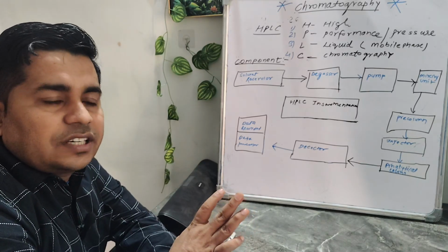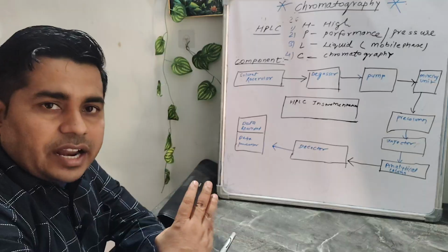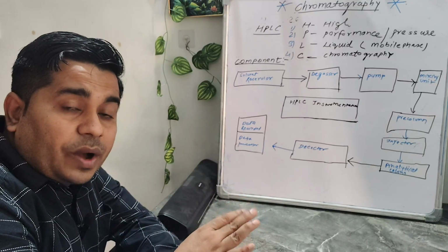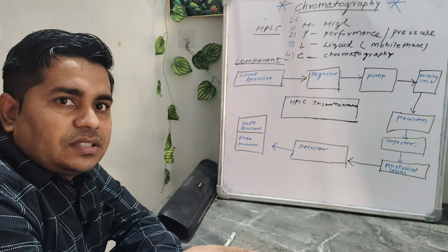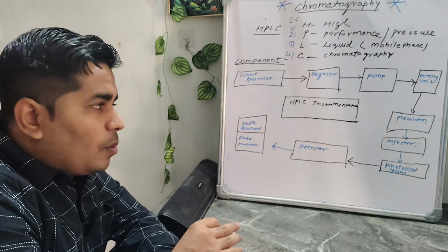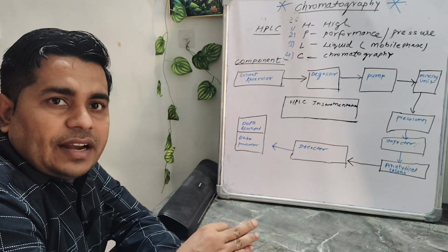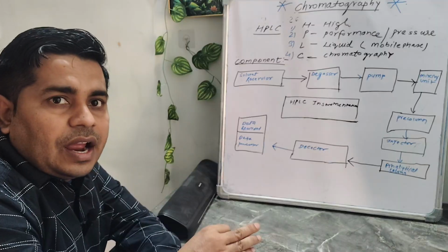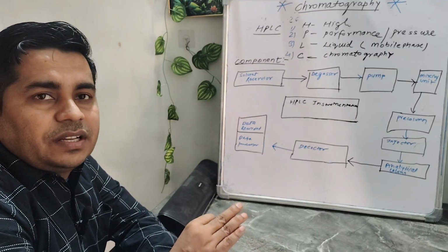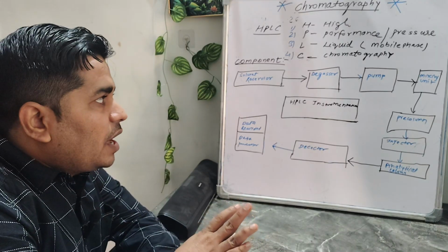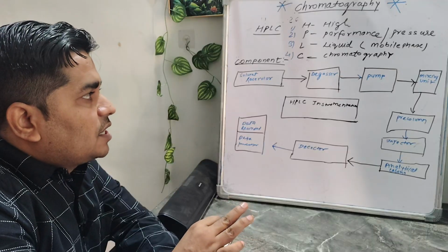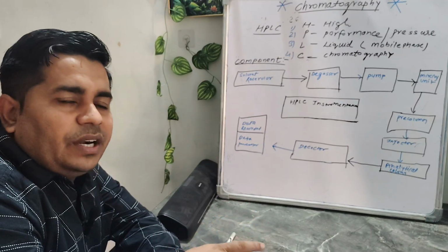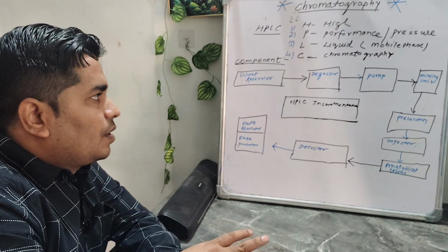Now the degasser, as the name says, means removal of dissolved gases for achieving a proper baseline and good peak shape, and to avoid any interruption in our instrument during the analysis. The degasser unit is also inbuilt in the HPLC system.